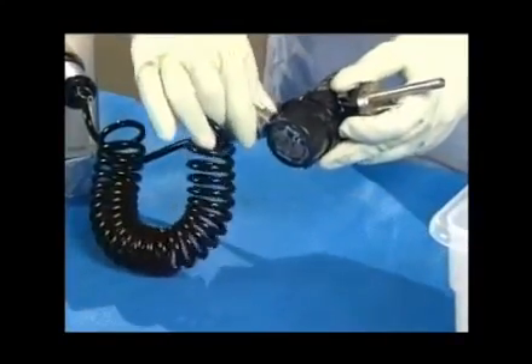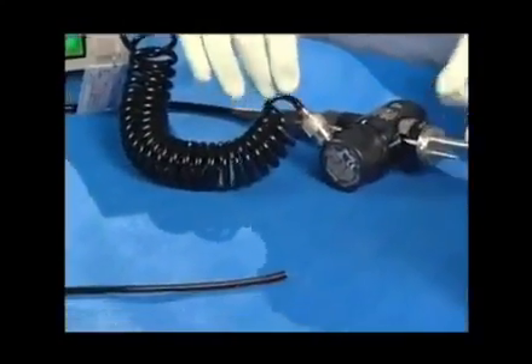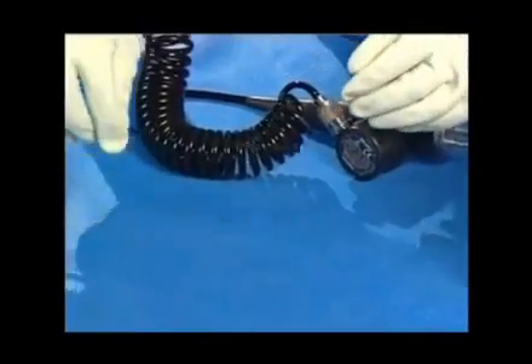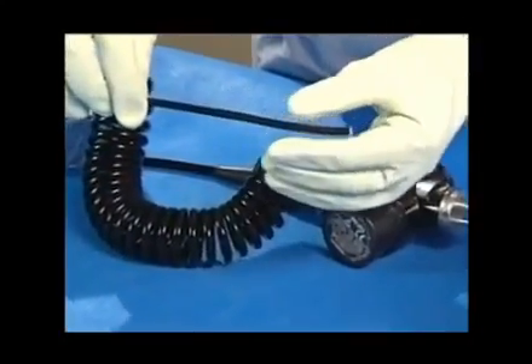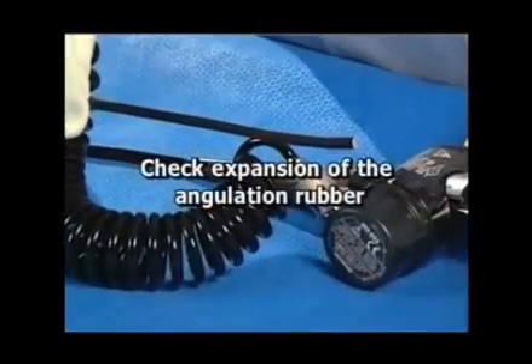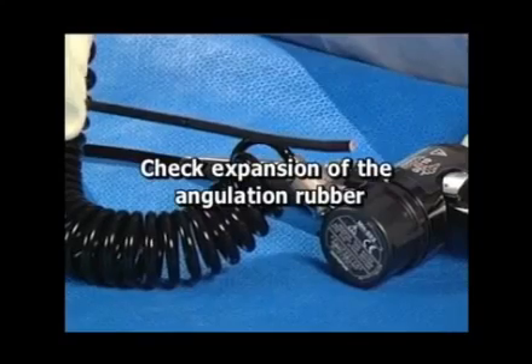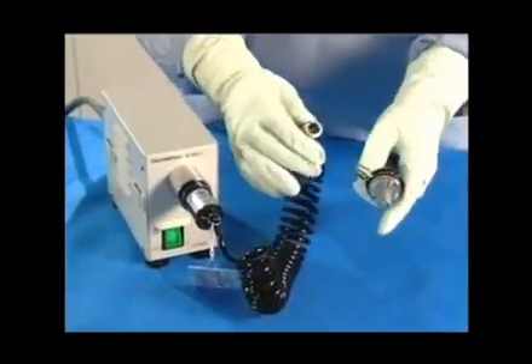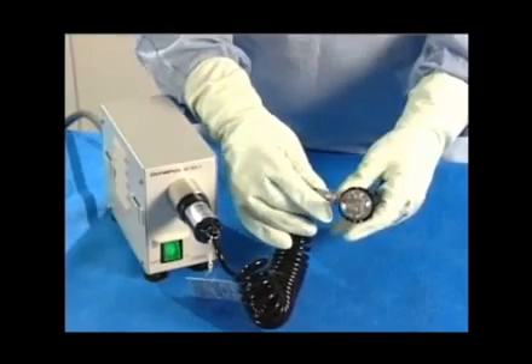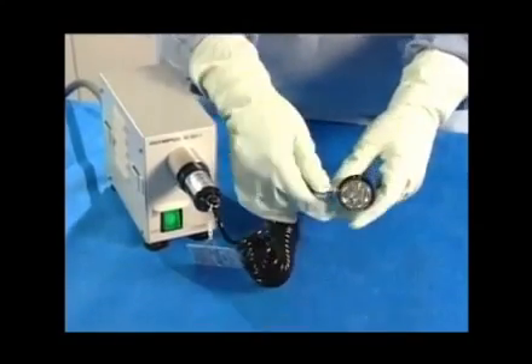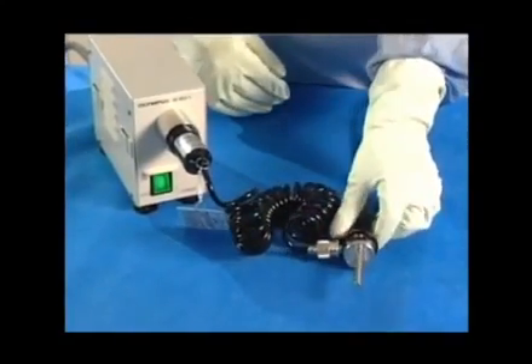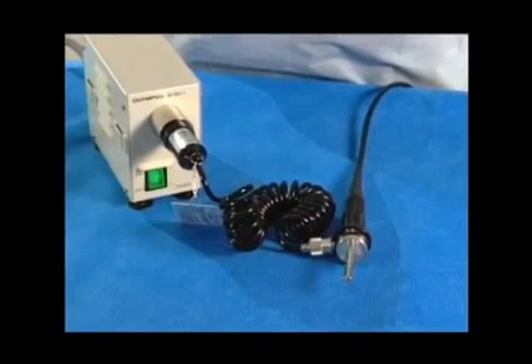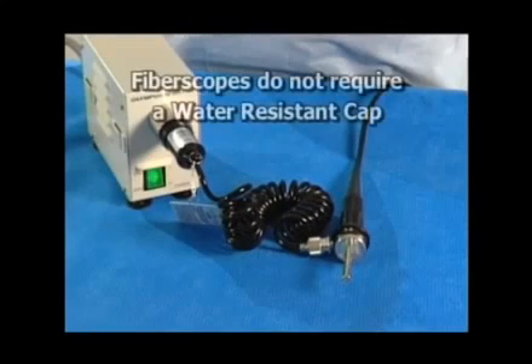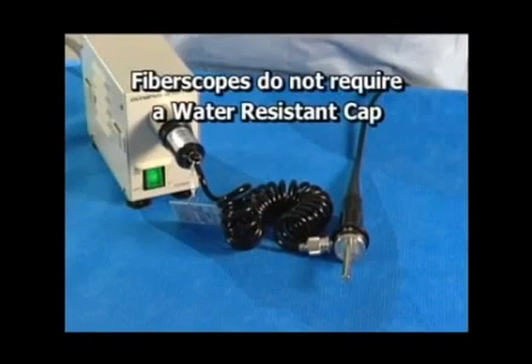Now, attach the leakage tester to the bronchoscope. As you pressurize the inside of the bronchoscope, the rubber sheath on the distal tip of the bronchoscope will expand. Note that if you are reprocessing a fiber optic bronchoscope rather than a video bronchoscope, the leakage tester is connected directly to the endoscope. Fiber scopes do not require a water-resistant cap.